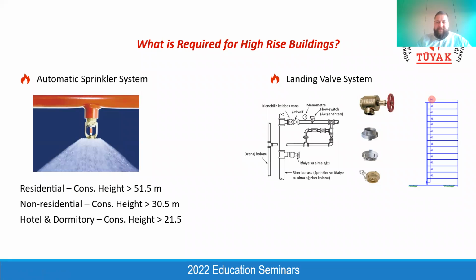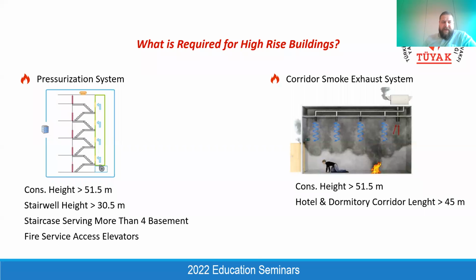And the landing valve system becomes mandatory for the high-rise building. It's combined with the sprinkler system. For this combined system, we are calling them water-based suppression systems altogether: the sprinkler system, landing valve system, and also the fire hose cabinets. But we will see how it will change our architectural design when we provide these systems.